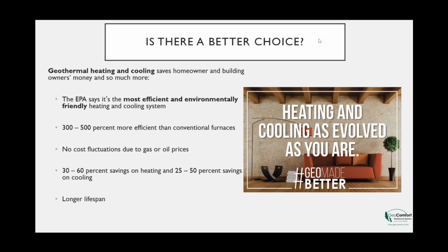And the other nice thing about geothermal systems, which I think is really overlooked, is the longer lifespan, especially the ground loop. The ground loop that you install is there for the life of the building. It's a one-time investment. It's basically pre-purchasing your energy up front by installing that system. So you no longer have to worry about cost fluctuations due to gas and oil. You buy it one time, you put it in the ground, and it's there for the life of the building. And that's 60 to 70% of the energy your home will need for the life of that building. So there is no better way to buy energy than to put a ground loop in. And again, that's going to be there for the life of the building.